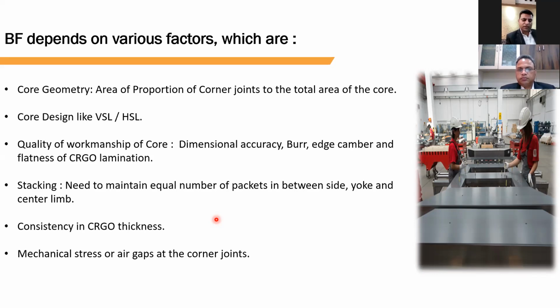But generally what happens is that if there is a breakdown or any quality error during the process, the CRGO processor forgets to replace the defective lamination with the correct one, and supplies it as is. The transformer manufacturer finds it during core assembly, and if there is any break in the packets, the excess packets available at the transformer manufacturer's side go to waste.